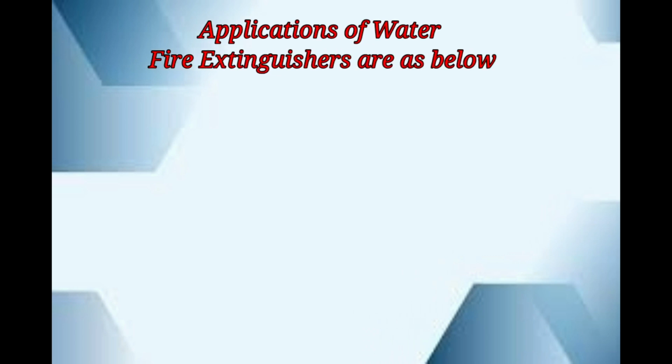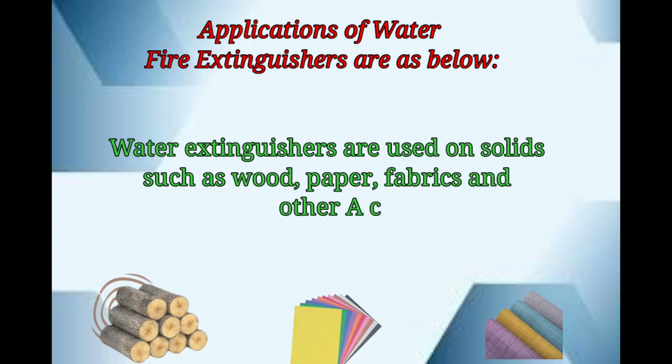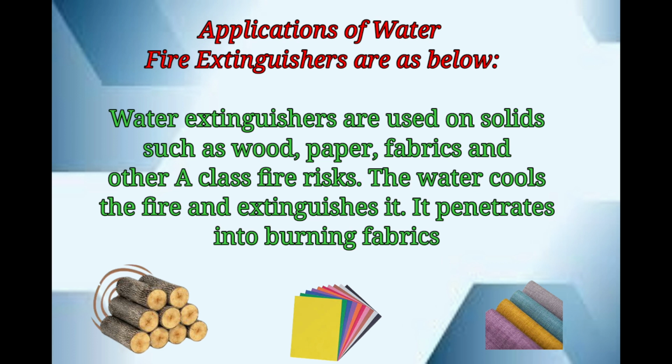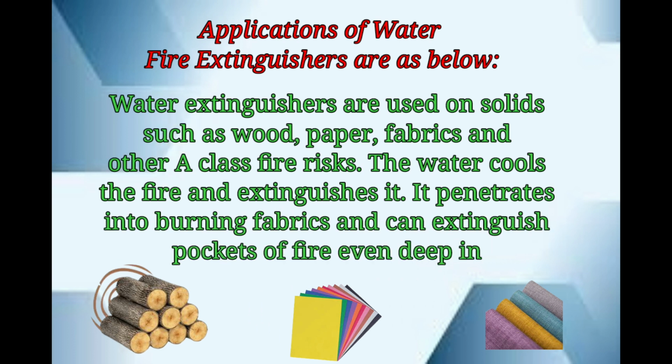Applications of water fire extinguishers are as below. Water extinguishers are used on solids such as wood, paper, fabrics, and other A class fire risks. The water cools the fire and extinguishes it. It penetrates into burning fabrics and can extinguish pockets of fire even deep in the core of the fire. So these are the 3 types of material on which water fire extinguishers are used.